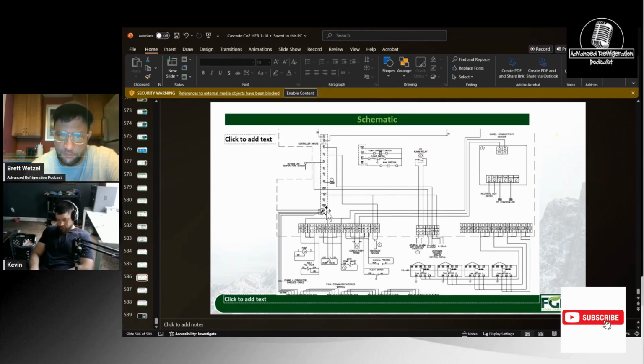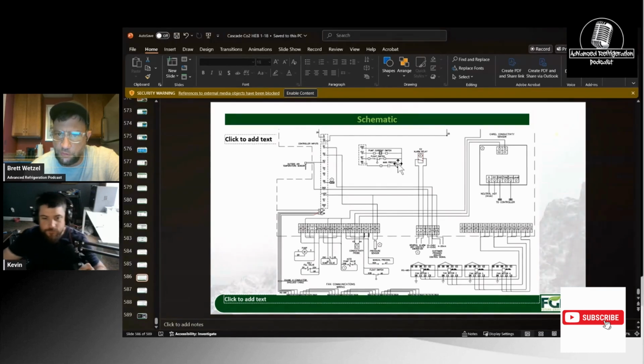So basically Modbus is from this controller right here. Here's some of the stuff that's in the inputs here. You have a float input, manual pre-cool, and the pump current switch, which is basically your proofing switch for that pump.